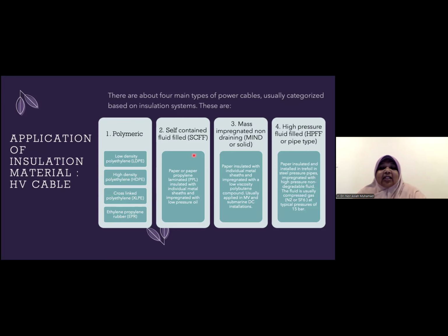The second type is self-contained fluid filled cable: paper or propylene laminated, insulated with individual metal shields and impregnated with low pressure oil. Then we have the third type, which is mass impregnated non-draining cable, which is paper insulated with the individual metal shield and impregnated with a low viscosity polybutene compound. It's usually used in medium voltage and also submarine DC installation.